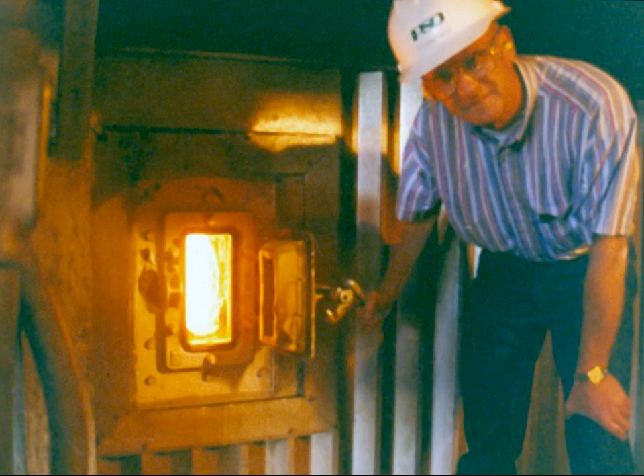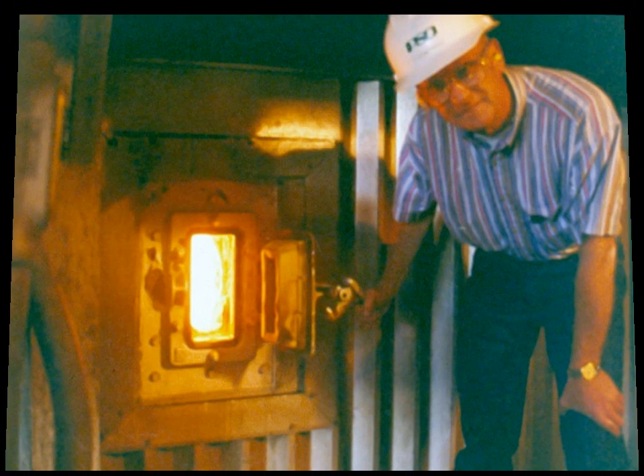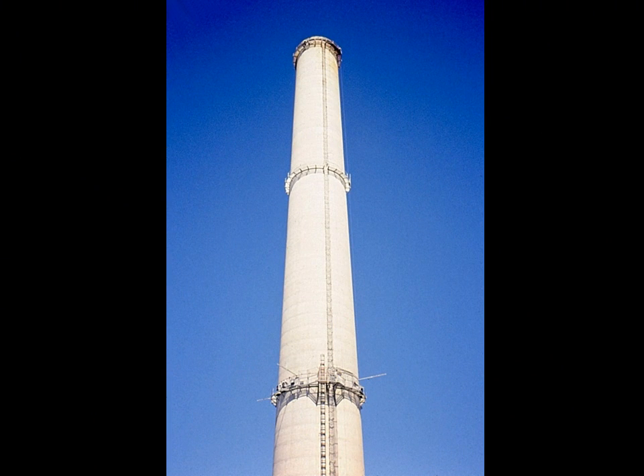The purpose of any power plant boiler is to heat water into steam. Here we see Briggs by one of the plant's coal boilers, which burns coal to heat water to 1,000 degree Fahrenheit steam. Not all of the coal entering the boiler can be burned. The unburned heavy ash falls to the bottom and is removed for use as road base and cinder blocks. The lighter fly ash goes up the smokestack where it is given a negative charge and drawn off by an electrostatic precipitator, and this material is used in concrete and cement.